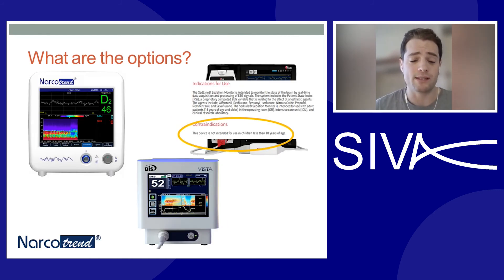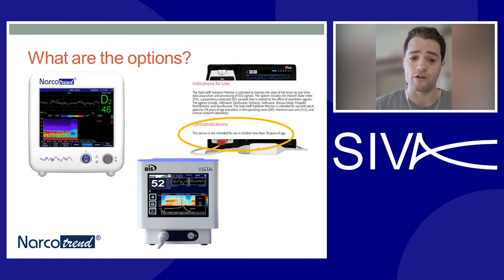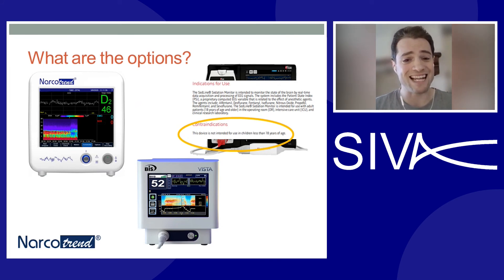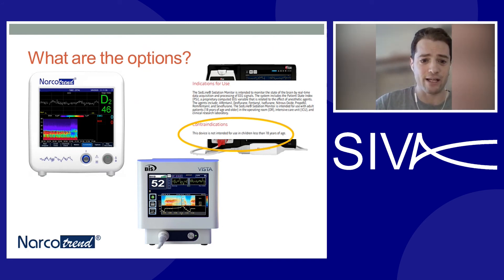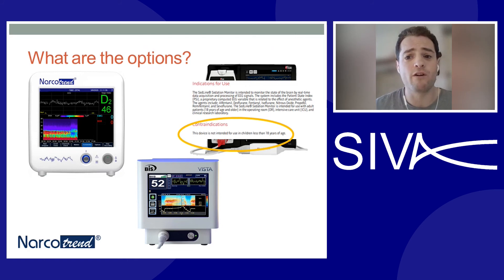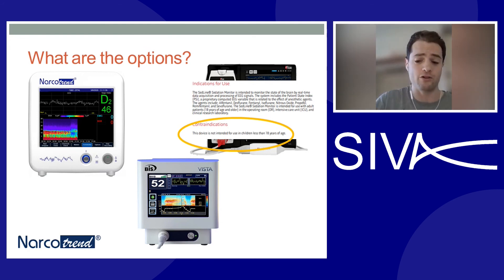What are the options for processed EEG monitoring in children in the UK? Fundamentally, you have three choices: the Narcotrend, the BIS monitor delivered by Medtronic, and the SedLine via the Masimo route. The SED Line — taken directly from their manual — states that the device is not intended for use in children less than 18 years of age, and the sticker itself is very large and hard to apply. That functionally leaves two options: the BIS and the Narcotrend.